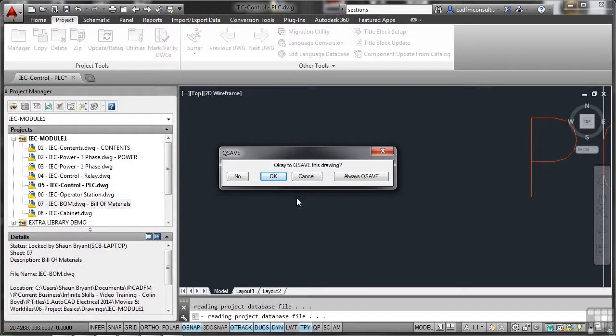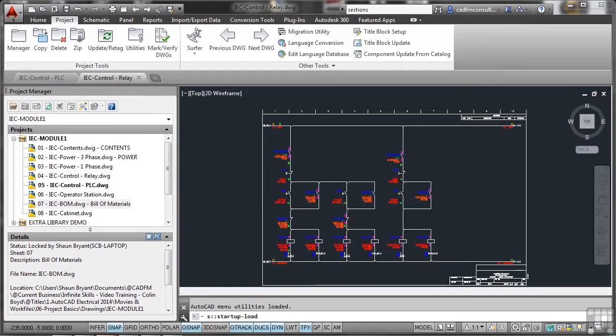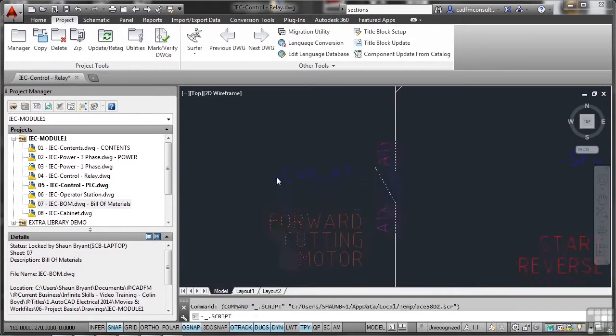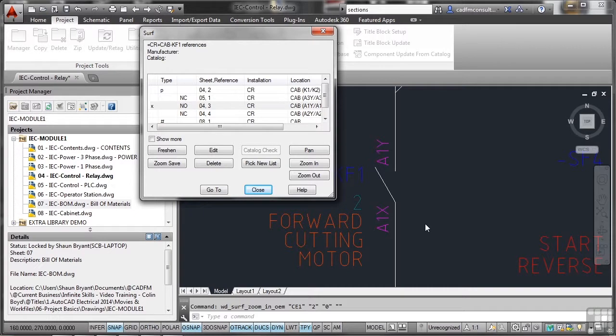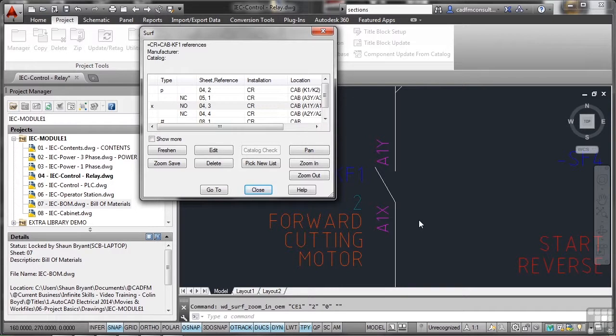What I can do there as well is I can select O4 like that and go to it. Do I want to save that drawing? Yes I do. I'll save that drawing. It then opens up another drawing and takes me to drawing four, the relay that works with the forward cutting motor. How cool is that? I don't have to go and find the drawing with it in because I've linked that using the database behind the project and linking objects within the database in AutoCAD Electrical. I can actually move from one drawing to another but using components rather than the arrows or the surfer.